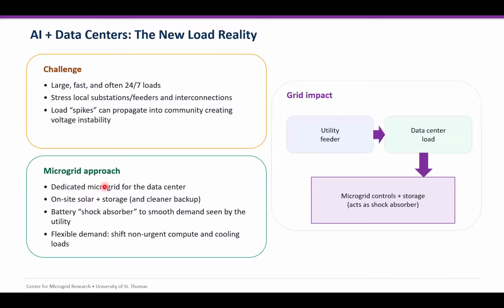There is a microgrid approach to deal with these data centers, by having a dedicated microgrid for the data centers with on-site solar and storage, and the battery will act as a shock absorber to smooth the demand seen by the utility. This is what I mean by the load spikes. The batteries will be able to absorb these spikes, and there is flexibility in demand, so we can shift non-urgent computing and cooling loads as well. So we have the utility feeders, we have the data centers, and we have the microgrid control and the storage, which act as a shock absorber.